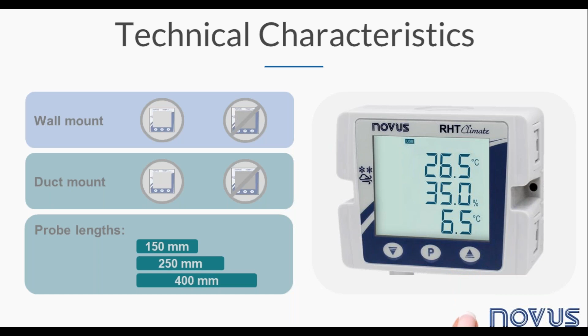The wide display has backlight and may show 3 variables on screen from all psychrometric variables. It also presents icons and other information like alarms, maximum and minimum, and also communication status. The duct mount type has a measuring range of -40 to 100 degrees Celsius. The wall mount type is from -40 to 60 degrees Celsius, in which only the probe is in contact with the measured medium. The indicated resolution for both measured variables is 0.1 degrees Celsius and 0.1% of RH.